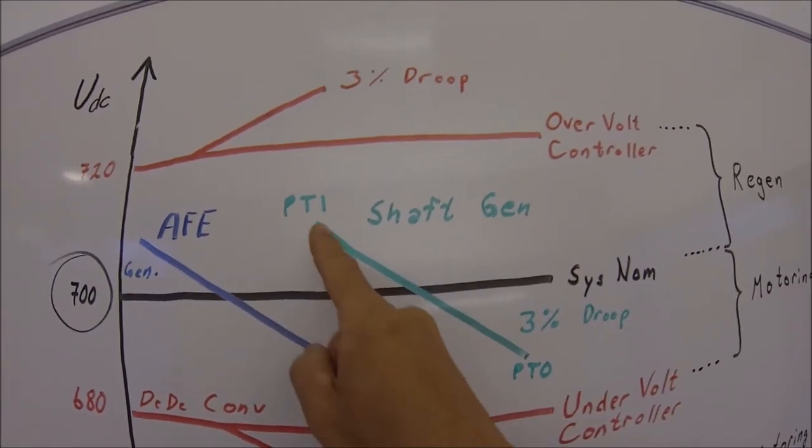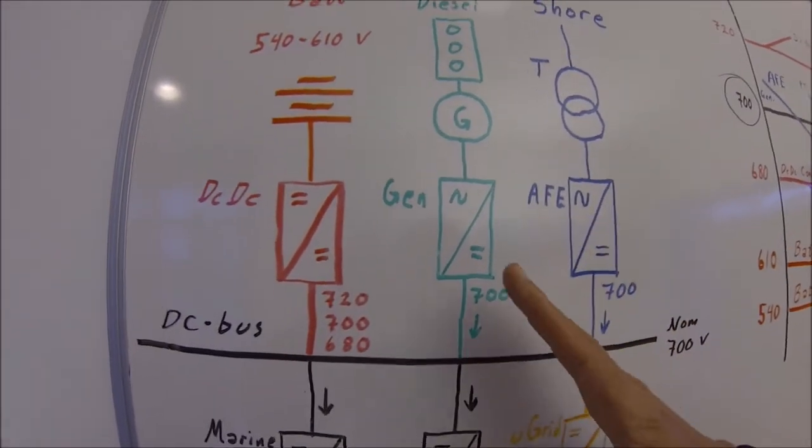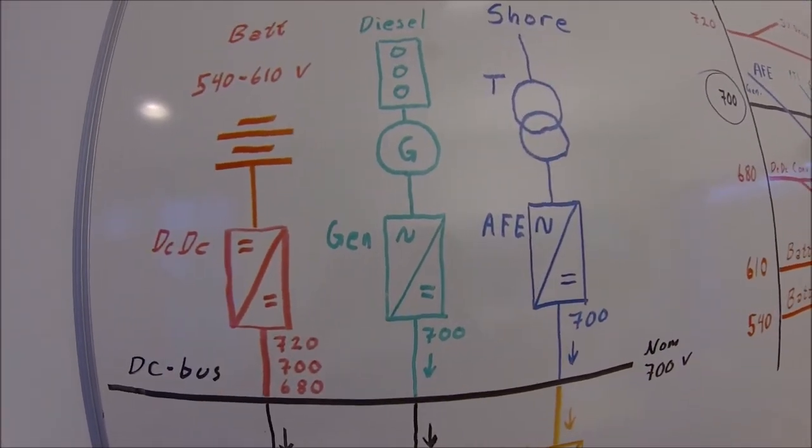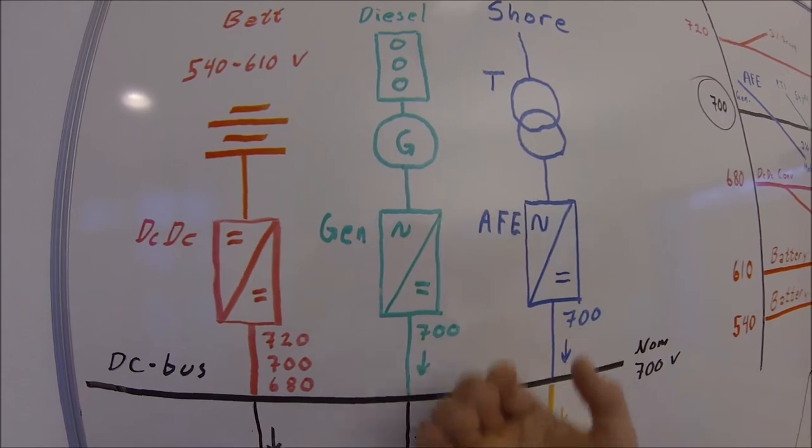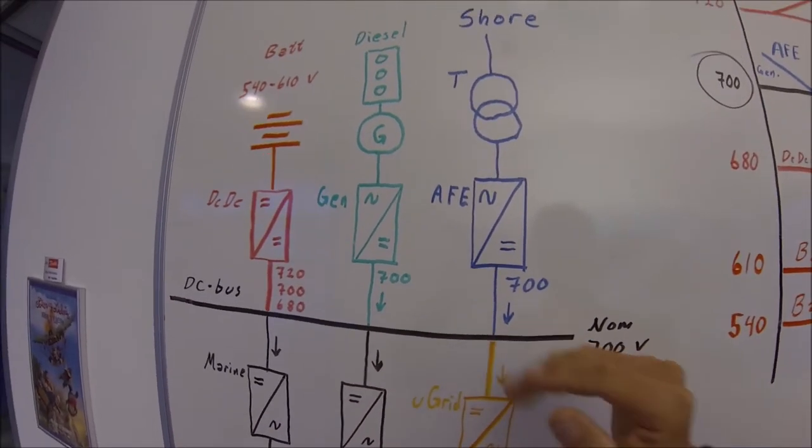Then you can do exactly the same on the shaft generator. The shaft generator will then act very similar to the active front end. And when we pull energy out of the system, the voltage will droop synchronized to the active front end.